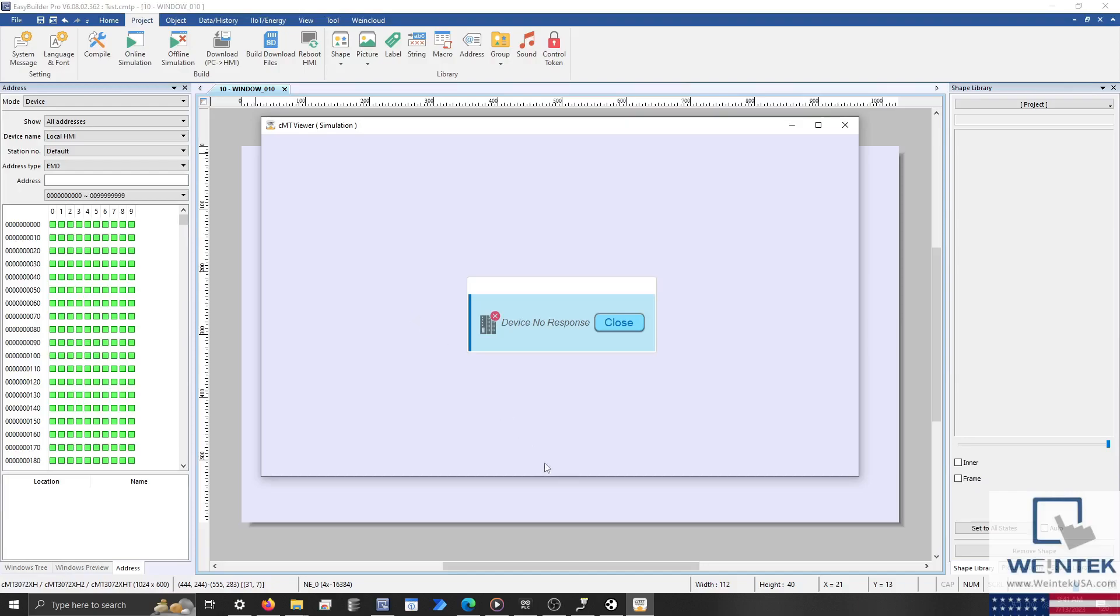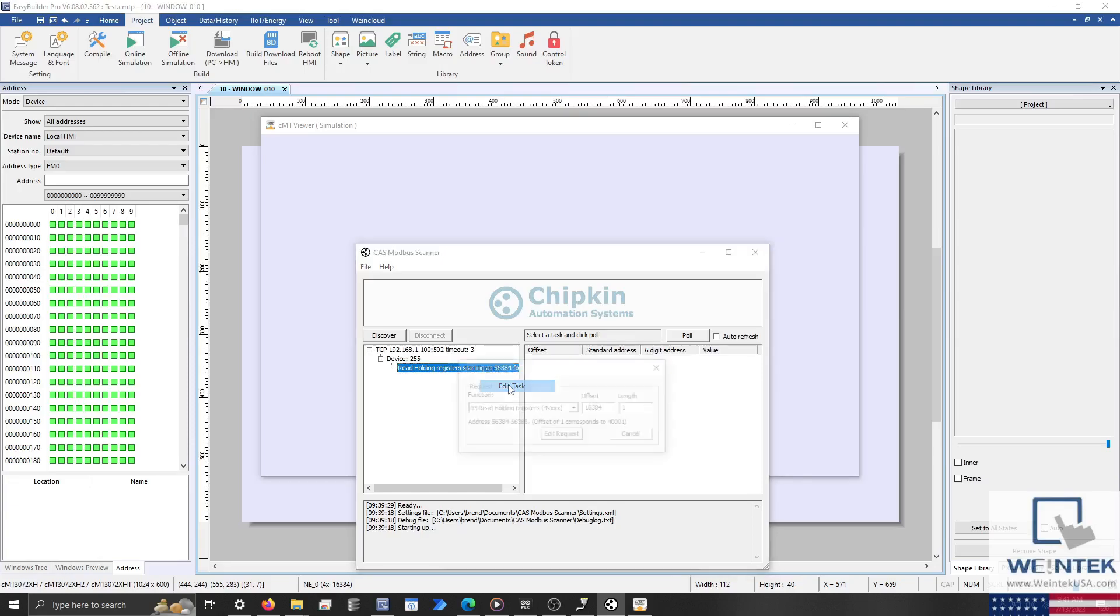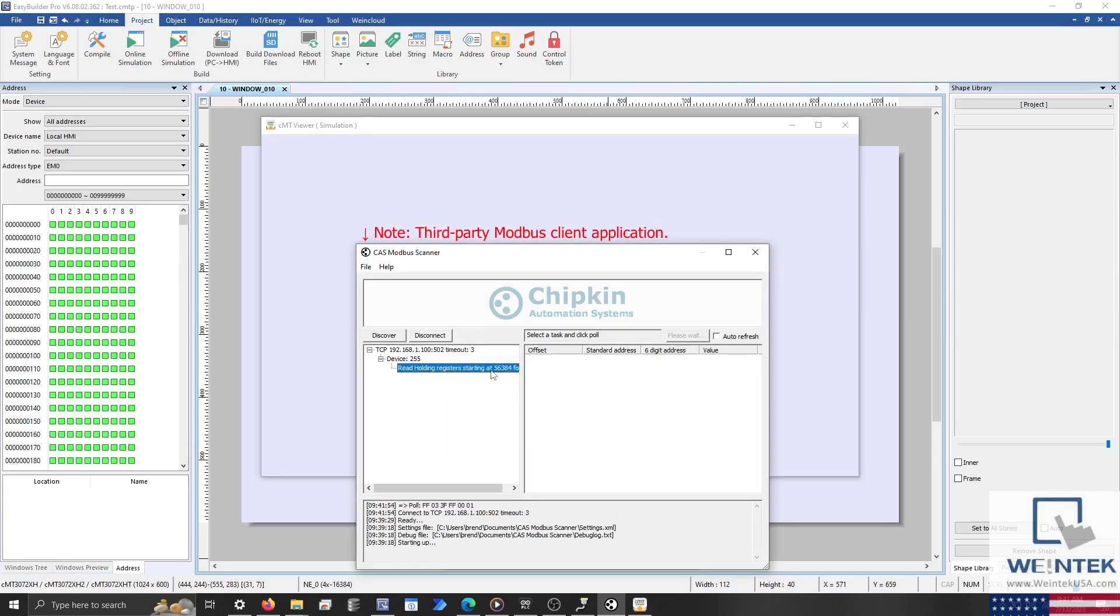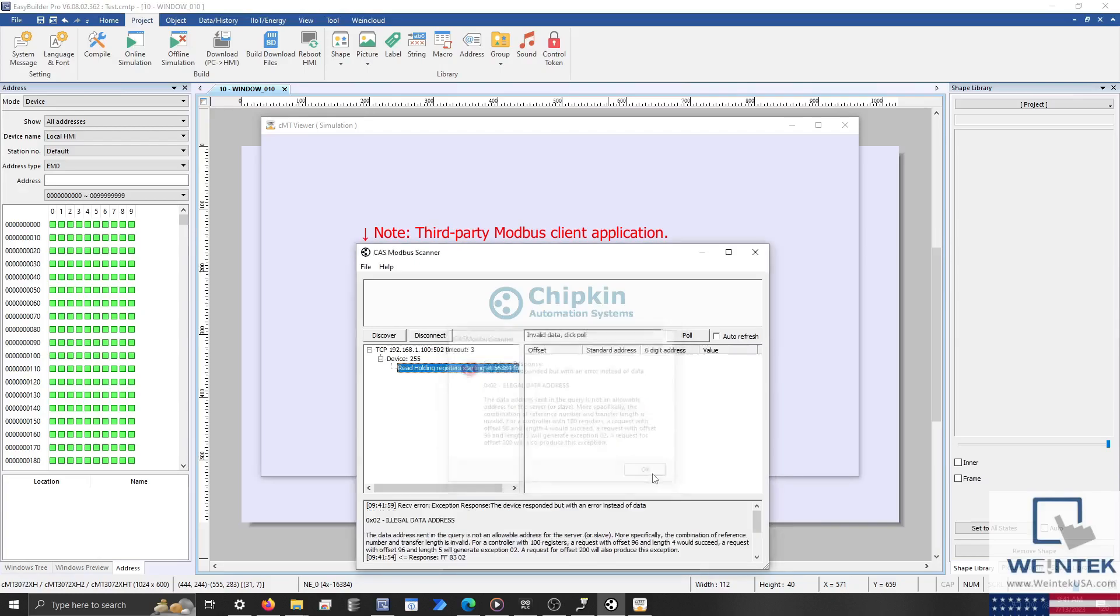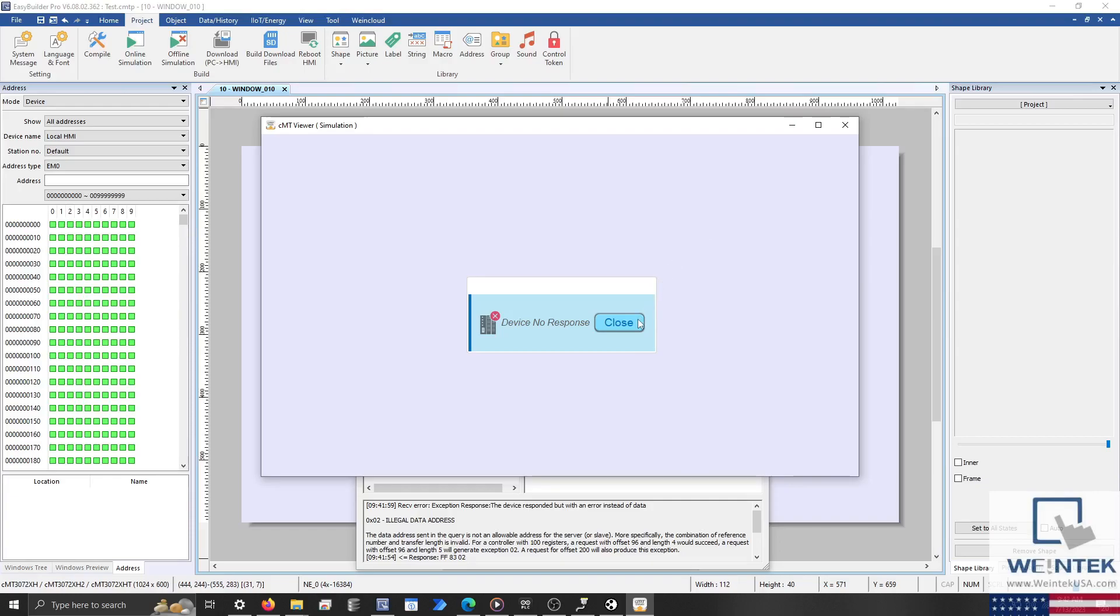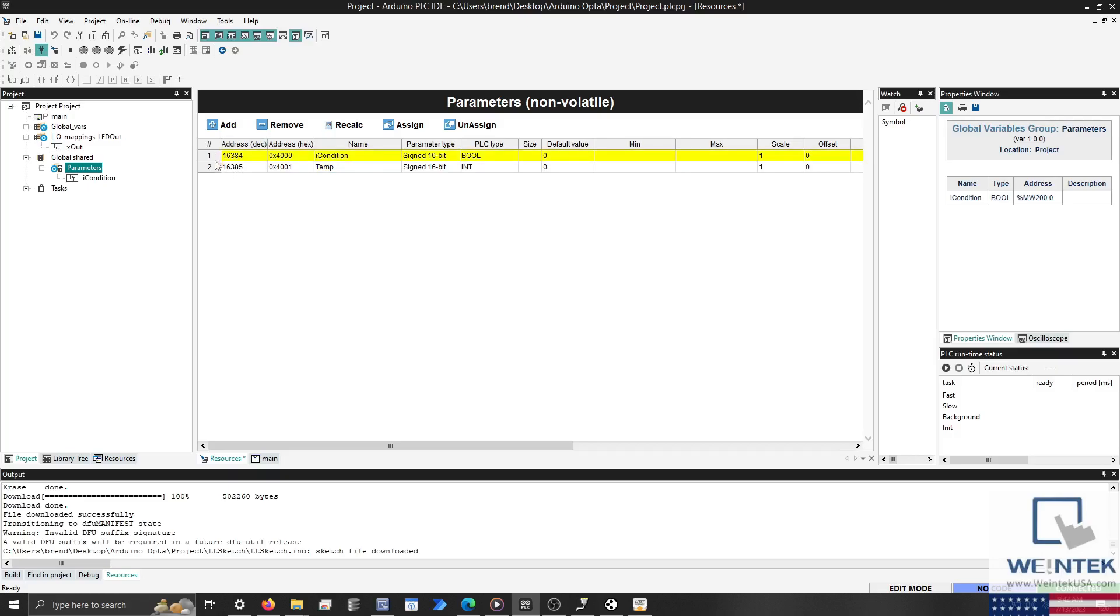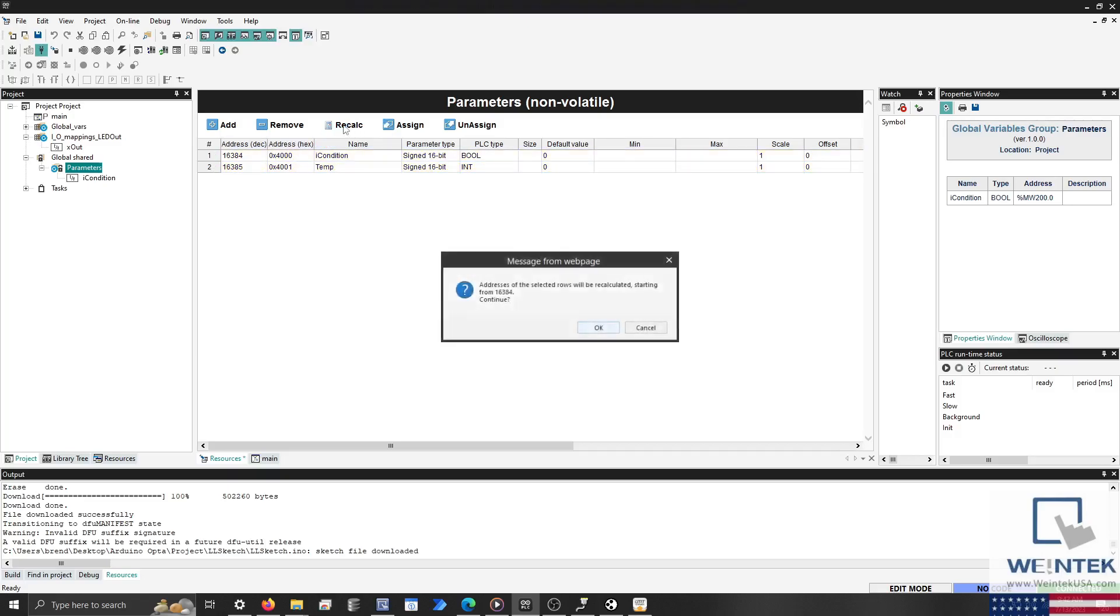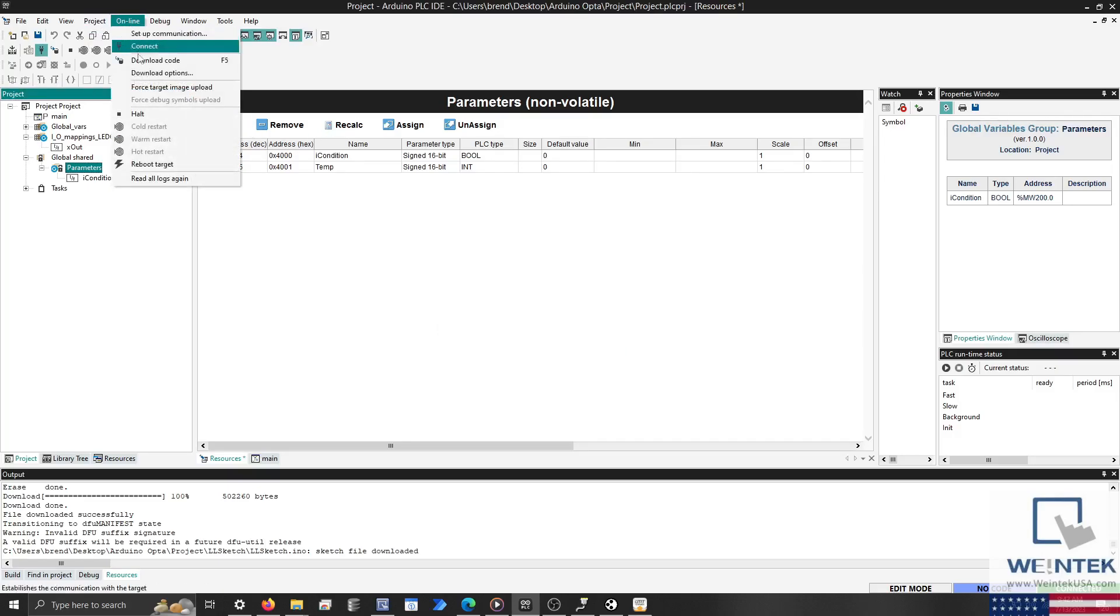On occasion, you may encounter a Device No Response message. This occurs when the HMI fails to read an address or tag within an external device. I have noticed that this can occur when only one Modbus address is present within the Opta, and have found that adding an additional Modbus address and recalculating each address may resolve this issue. Just don't forget to download the updated program to the PLC when finished.